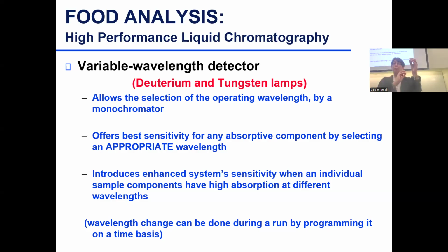Some detectors have both lamps, so you can switch them both on depending on the analysis, or switch one on and turn the other off if you care for one or the other spectrum.